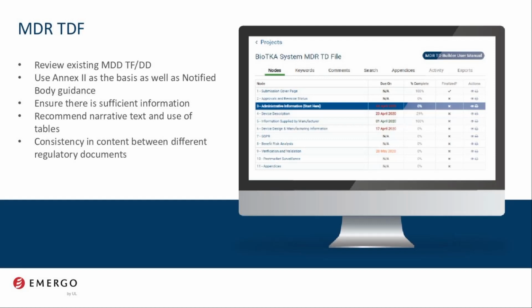So on the technical documentation file, a manufacturer should review their existing MDD technical file or design dossier. And while Annex 2 provides a structure and a format, we would recommend using that as the organization for a manufacturer's technical documentation file. That would be in conjunction with notified body guidance, because many of these notified bodies have now shared guidance on MDR compliance and the technical documentation file. And really, a manufacturer needs to ensure that there is sufficient information. One thing we want to make very, very clear, and we heard this from a recent BSI communication, is that even lower risk devices will be assessed as vigorously as the higher risk devices.